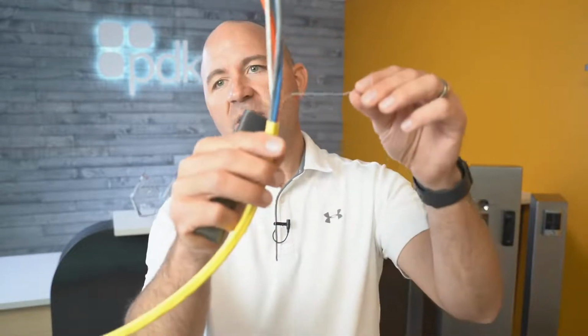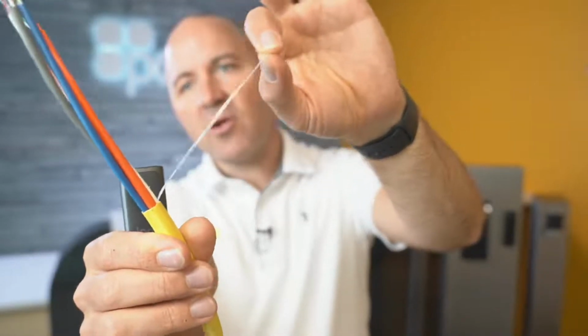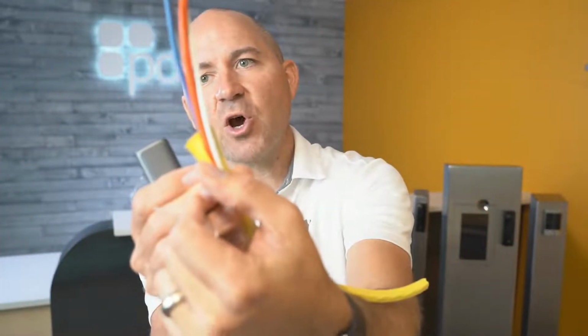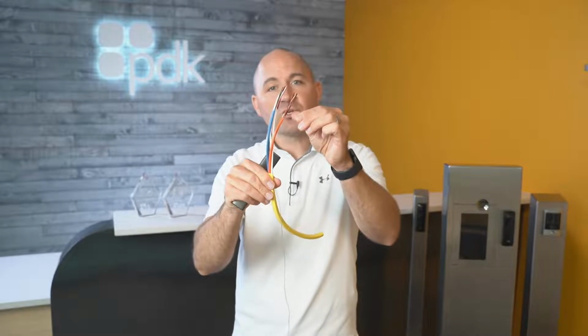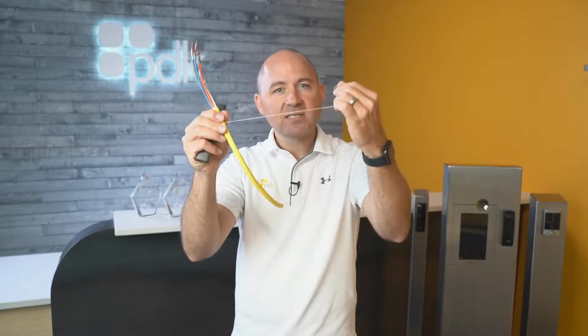You saw the banana cable on the slide, but I've got a piece of it here stripped back for you. You'll also see this little thread on the side. Once you get to the door and pull this banana cable, you may need to pull it back quite a ways to run down to the reader and then to the locking hardware and split that wire. This is a really nice feature for those not familiar with banana cable or individual strands - they all have this little nylon thread inside that lets you just grab it and peel the wire back.